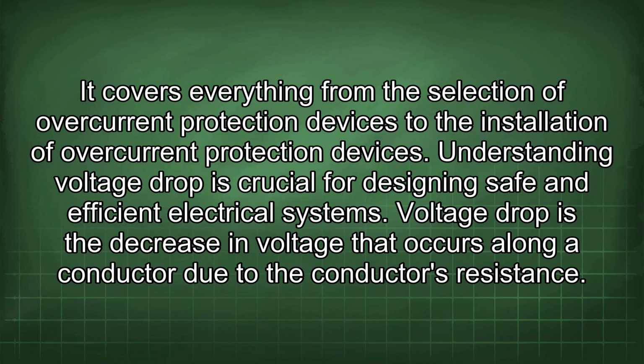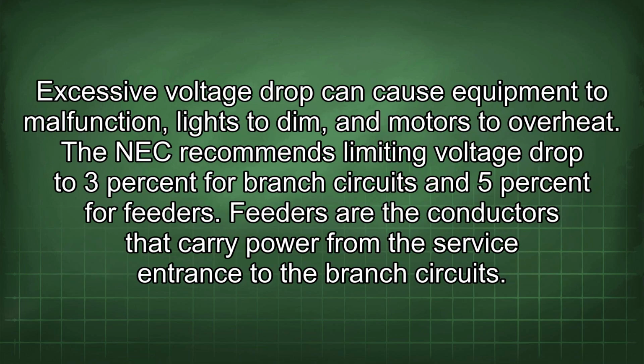Understanding voltage drop is crucial for designing safe and efficient electrical systems. Voltage drop is the decrease in voltage that occurs along a conductor due to the conductor's resistance. Excessive voltage drop can cause equipment to malfunction, lights to dim, and motors to overheat. The NEC recommends limiting voltage drop to 3% for branch circuits and 5% for feeders. Feeders are the conductors that carry power from the service entrance to the branch circuits.